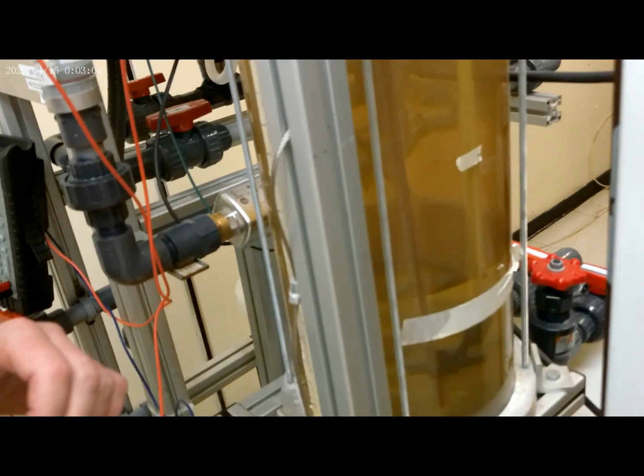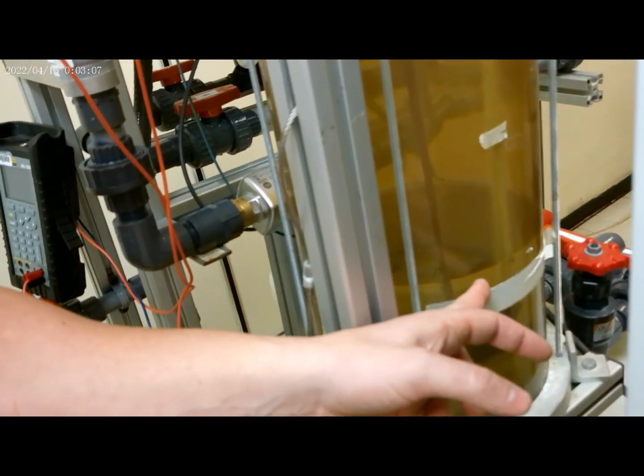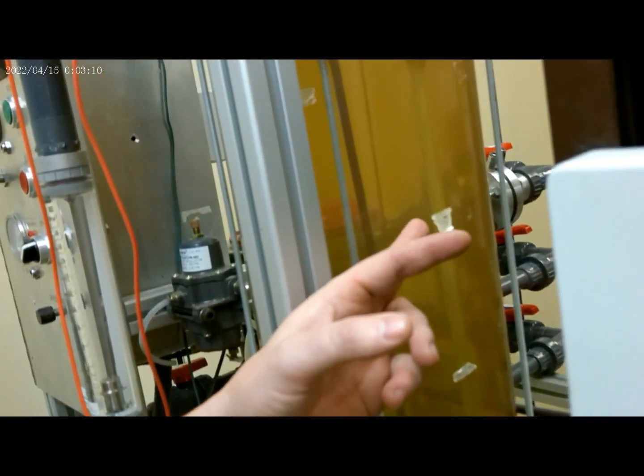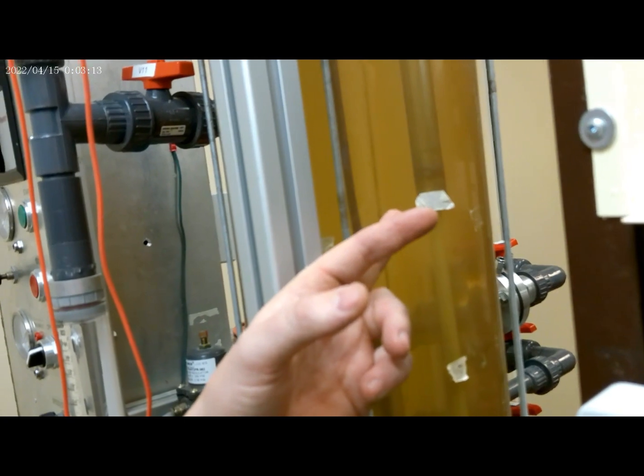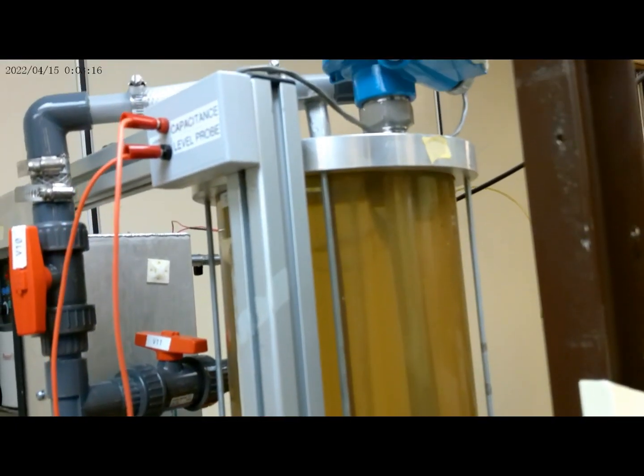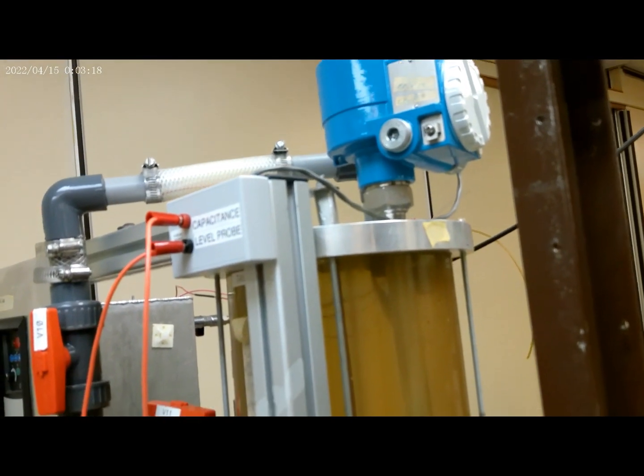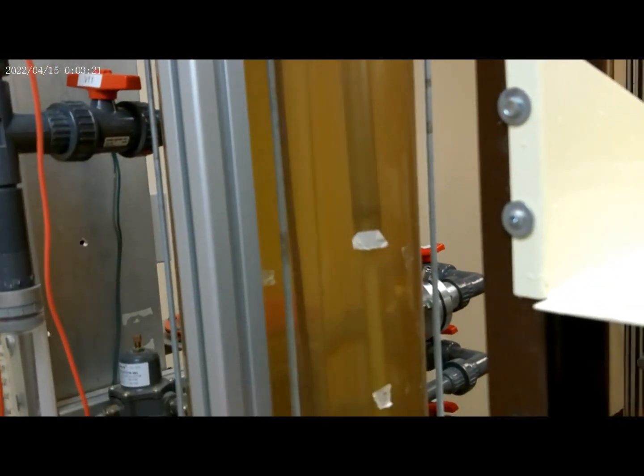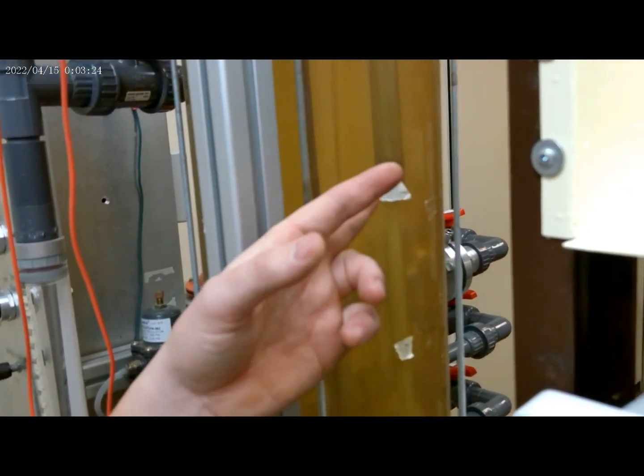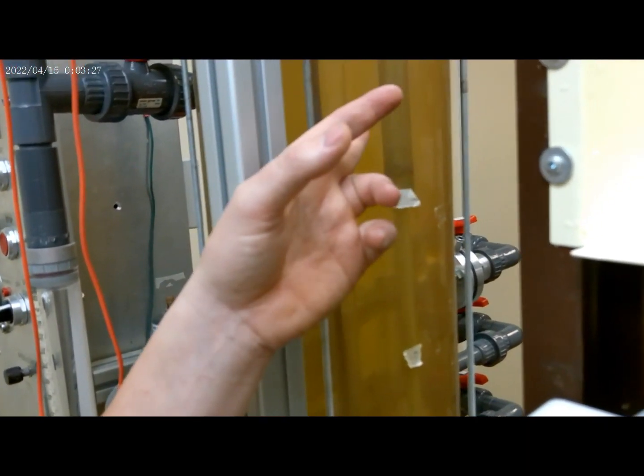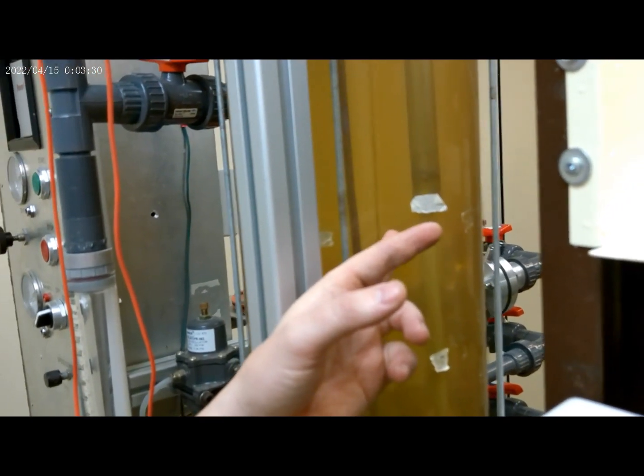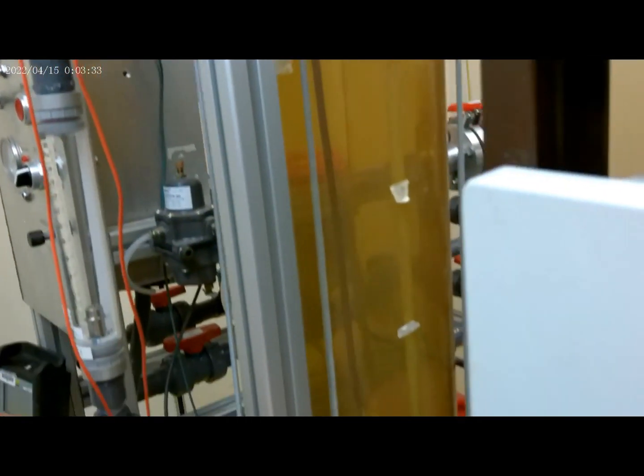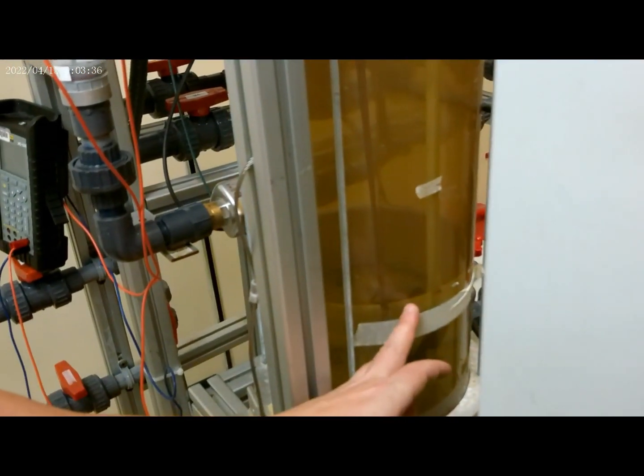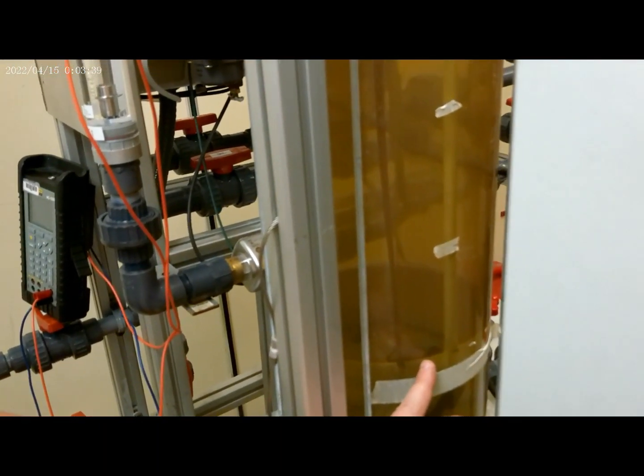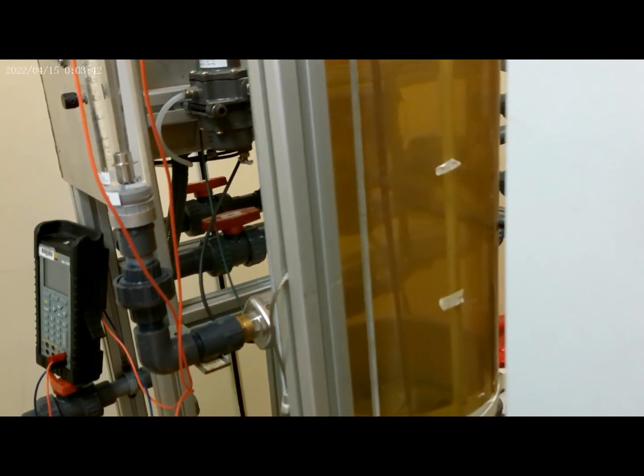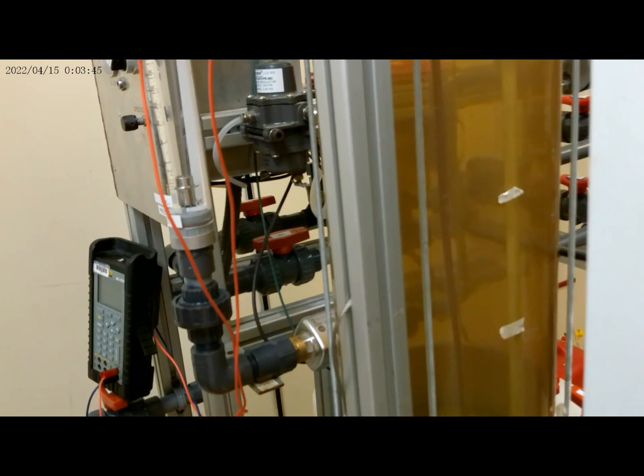Here we can see the capacitance probe is this white probe that goes all the way up, and here it hits stainless steel, then continues up to its head. Whenever you see it go from the conductive material into stainless steel, you know that's the full span of the unit. So from here down to the bottom, where our water level currently is, that is the full span we could ever do with this probe. We can't go more than that, but we can go less.